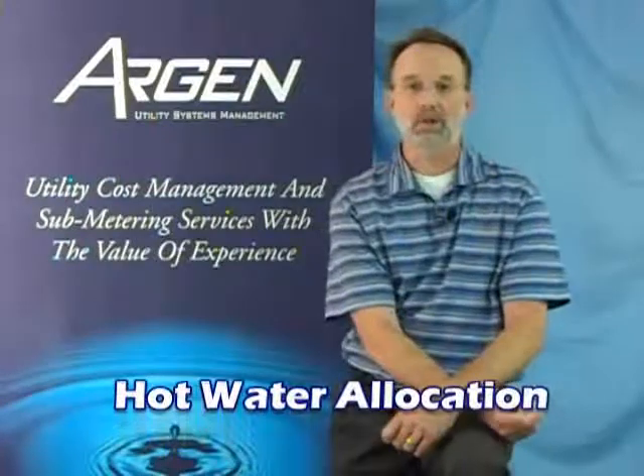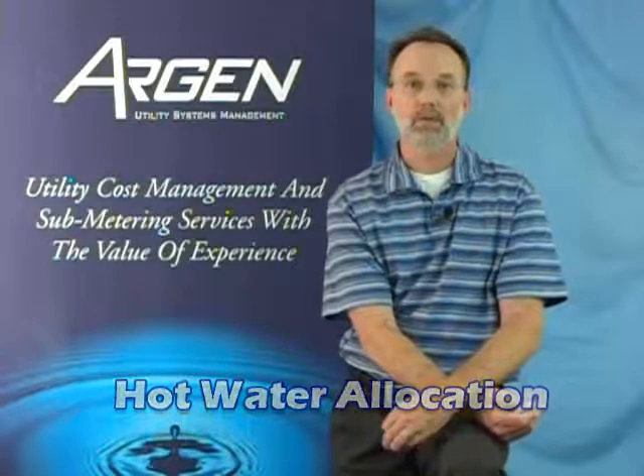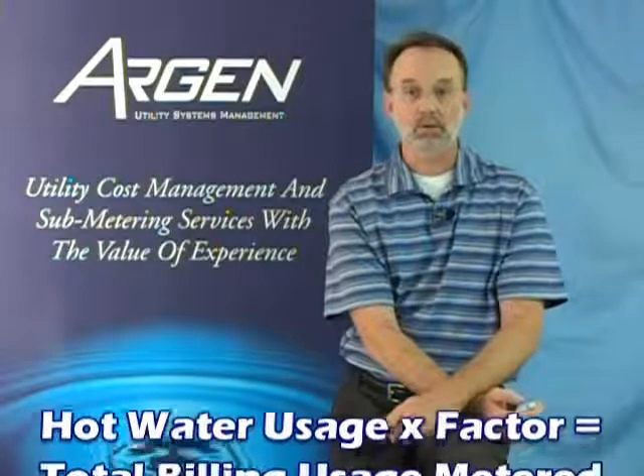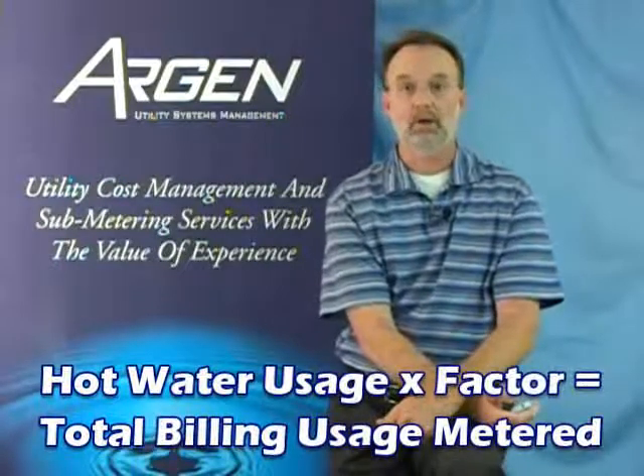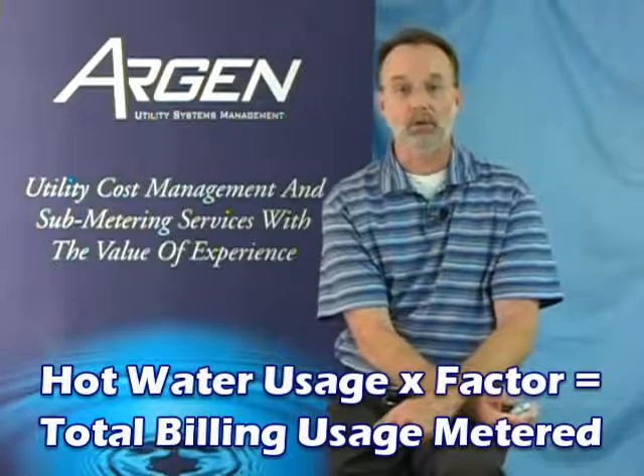Hot water allocation submetering is when the water meters are installed on the cold water inlet of the individual hot water heater. The measured hot water usage is multiplied by a factor to determine total hot and cold water billing usage. The multiplier factor is engineered for each property and in general ranges between 2 and 5. For example, a multiplier of 5 means that for every gallon of hot water used, a total of 5 gallons of water is used for billing purposes.